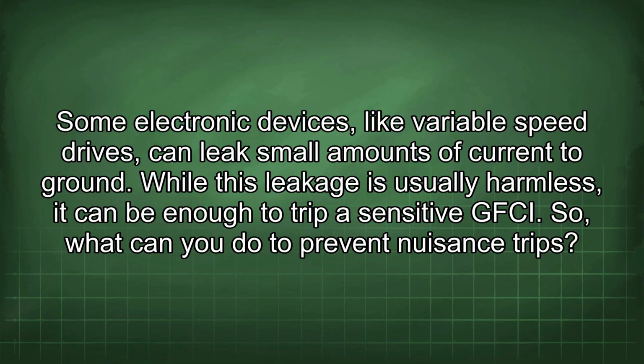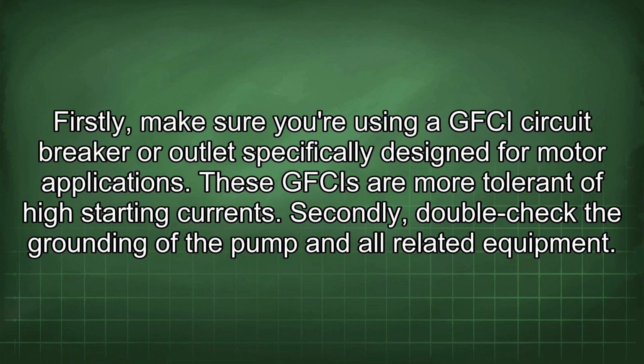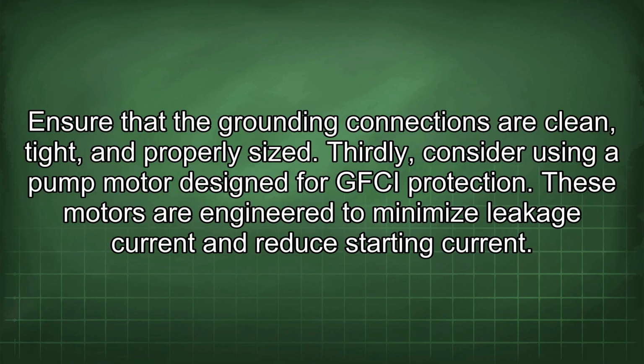So, what can you do to prevent nuisance trips? Firstly, make sure you're using a GFCI circuit breaker or outlet specifically designed for motor applications. These GFCIs are more tolerant of high starting currents. Secondly, double-check the grounding of the pump and all related equipment. Ensure that the grounding connections are clean, tight, and properly sized. Thirdly, consider using a pump motor designed for GFCI protection. These motors are engineered to minimize leakage current and reduce starting current.